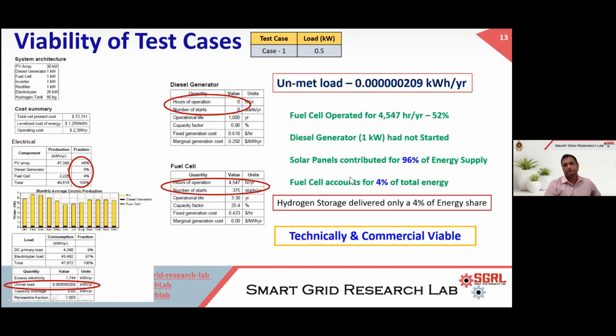For the viability test case, take for example case 1 for this particular location when the load is 0.5 kilowatt. The Homer modeling simply shows that the diesel generator had not produced a single kilowatt hour. The number of starts for the diesel generator is 0 for the year, meaning for this setup the diesel generator had not even started.